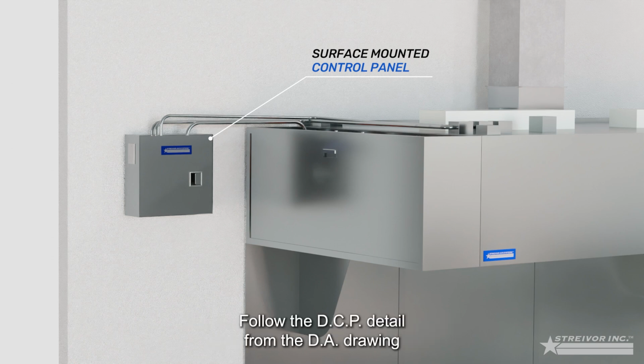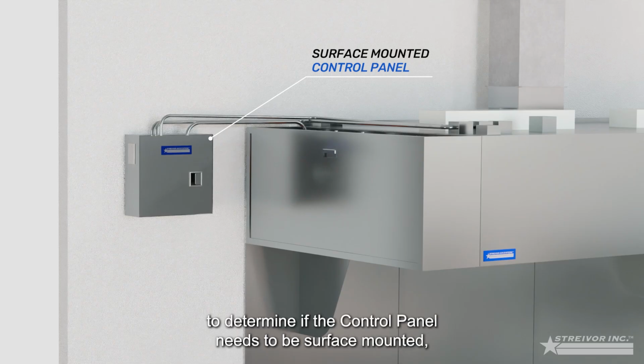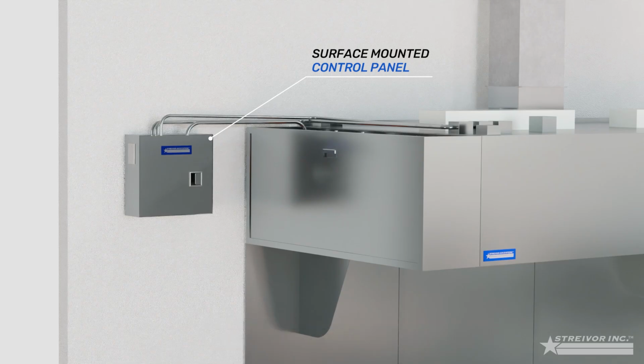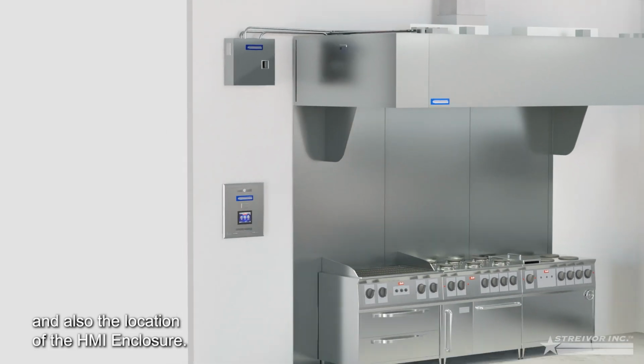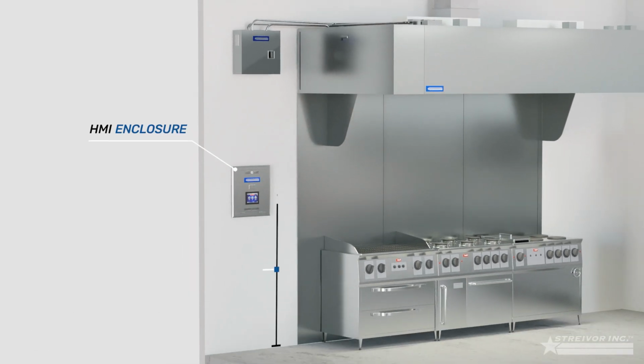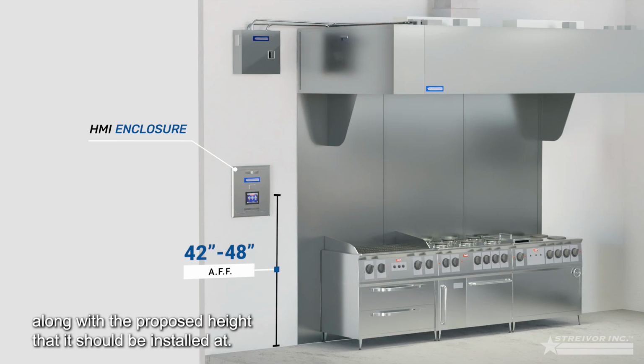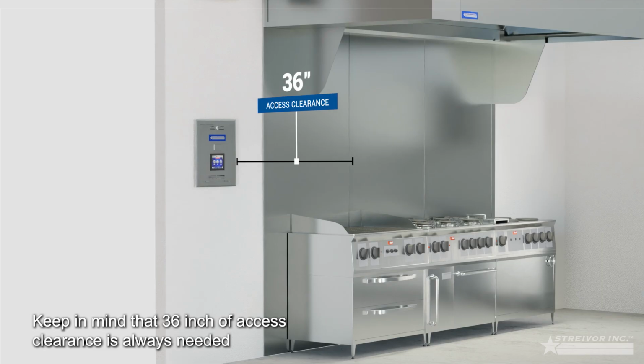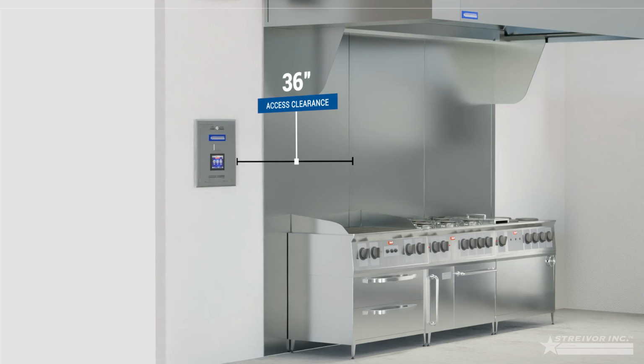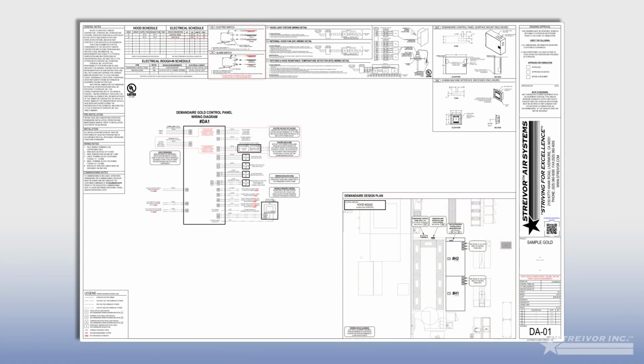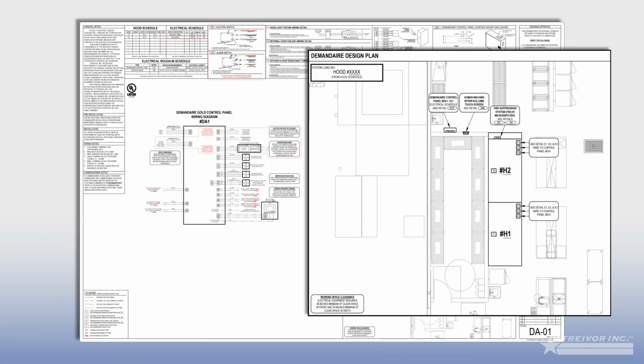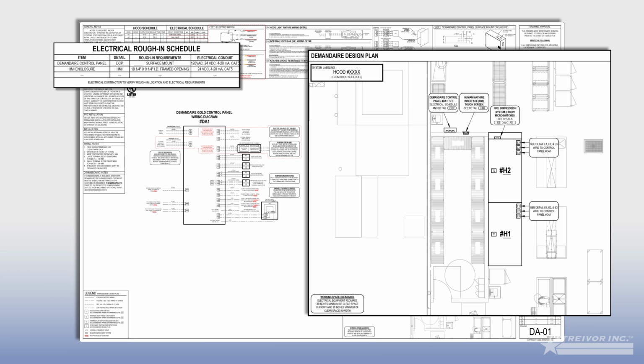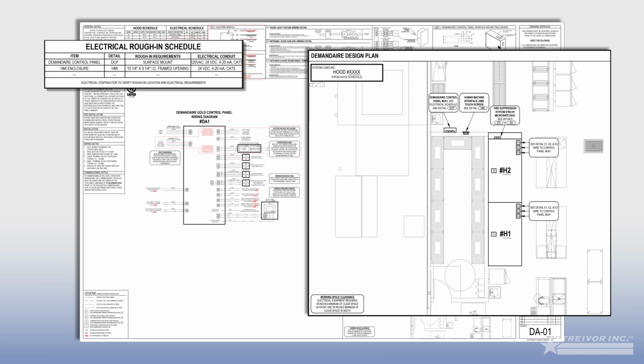Follow the DCP detail from the DA drawing to determine where the control panel needs to be surface mounted, and also the location of the HMI enclosure, along with the proposed height that it should be installed at. Keep in mind that 36 inches of access clearance is always needed in front of the HMI enclosure. The design plan conveniently shows the location of the applicable items, and the rough-in requirements section determines how electrical wiring should be brought to the control panel.